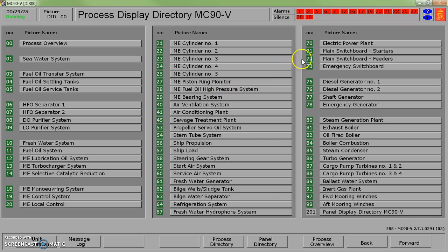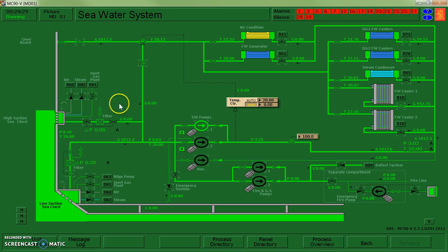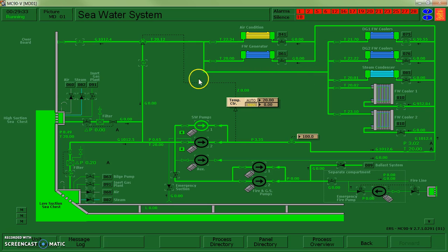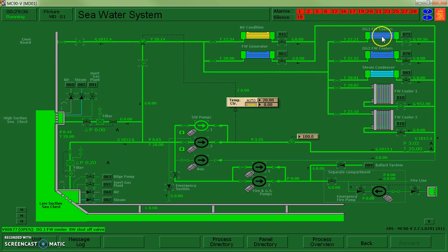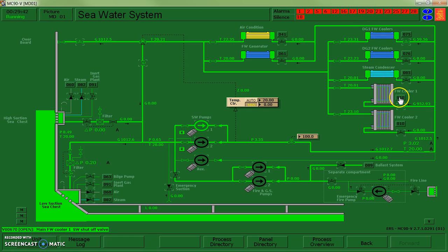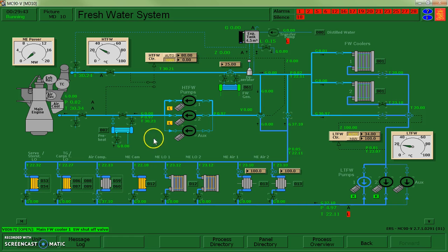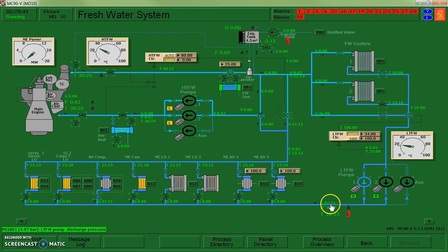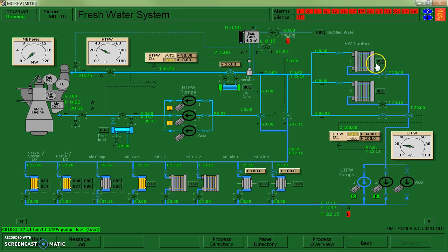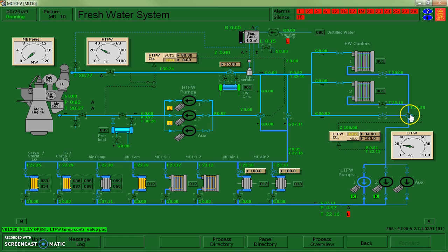So at this point, just to summarize our systems: I have my cooling water system, my main seawater system set up. I am supplying cooling water to my diesel generator as well as my freshwater system. My freshwater system is functioning. I have flow that's moving through it, cooling my air compressors. I've got a freshwater cooler as well as an alternate pathway and a control system that's now functioning for that system.